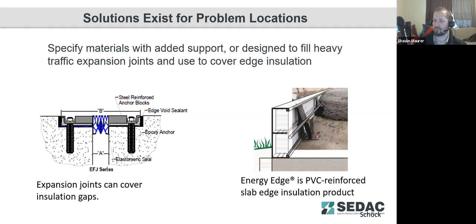We've also seen, for residential structures, if you've got a heated slab with a patio door or something that goes to the outdoors, you've got to be able to support the sill plate for the door. Probably the most common detail that we see is, again, that the insulation gets trimmed down and a strip of wood is laid there. Even though wood's not the ideal thermal break, it's better than having concrete poured on top of that, because concrete is much more conductive than wood is.